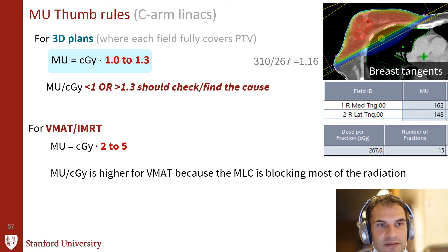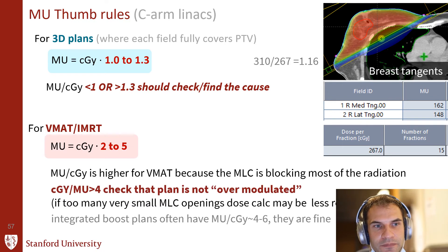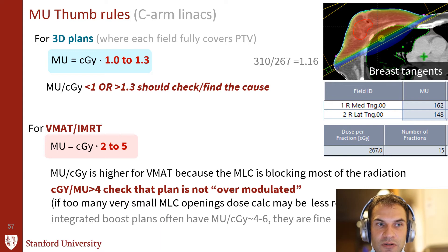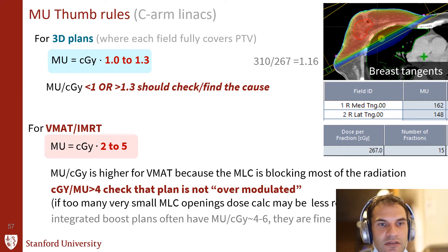For VMAT, the thumb rule is a bit less useful because MUs can typically be much higher than the dose per fraction. That's because the MLCs are blocking most of the radiation most of the time. We do like to keep it reasonably low. In general, a very high ratio of MU per centigray typically indicates that the MLCs are opening many small openings, and the dose delivered through small openings can be a little less reliable.